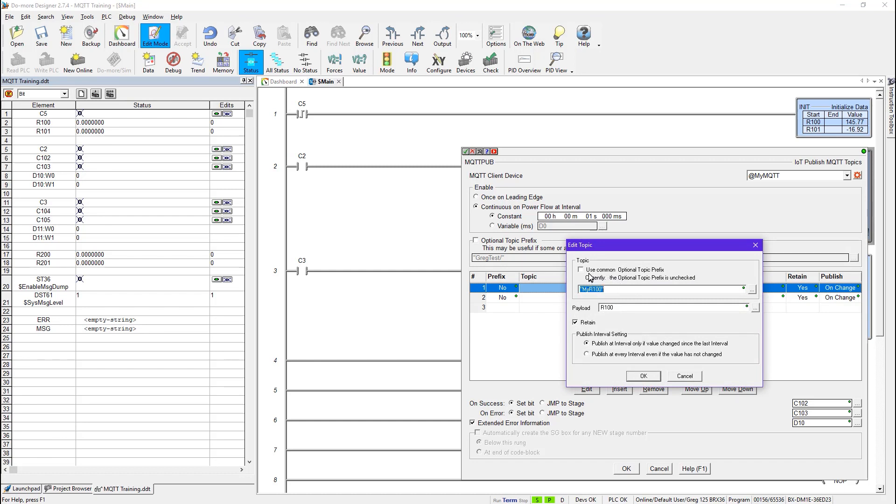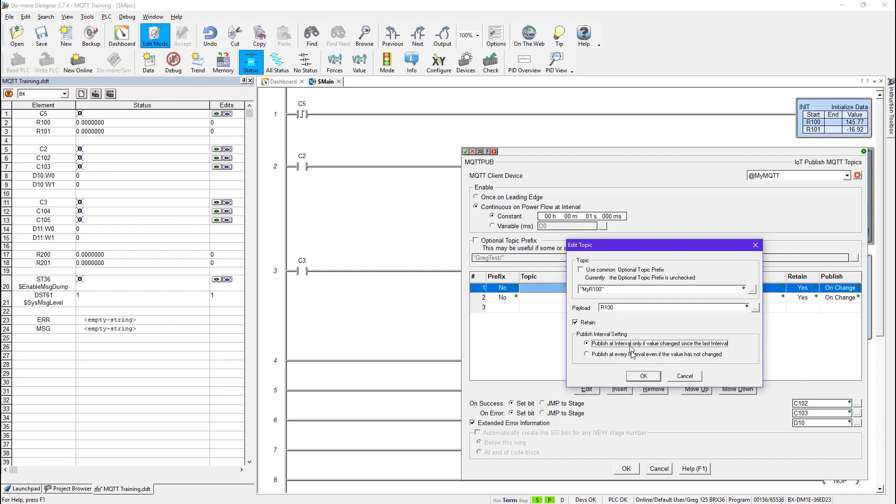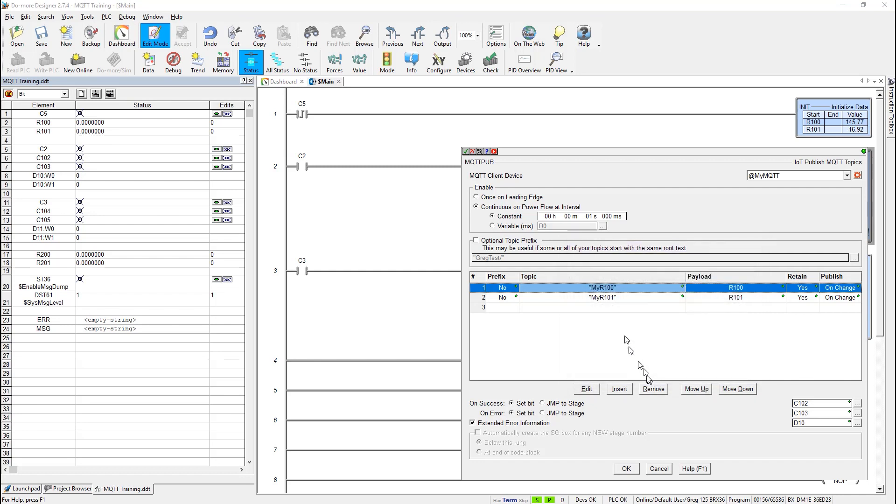So what this looks like is very simple. Here you can see I could use the common optional topic prefix as well if I wanted to here or not. That means if I had this checked, then this optional topic prefix would come into play. If it's unchecked, then not. So that way I could have topics down through here that use this optional topic prefix and some that do not. So here I called it my r100 and I gave it, told it to send the value that's stored in r100. I told it to retain. And then also here I have the publish interval setting. And this tells you how, this is the setting right over here in this column. Publish at an interval only if the value changed since the last interval. Or publish at every interval even if the value has not changed. That should be clear enough. So I made these two topics here to publish.